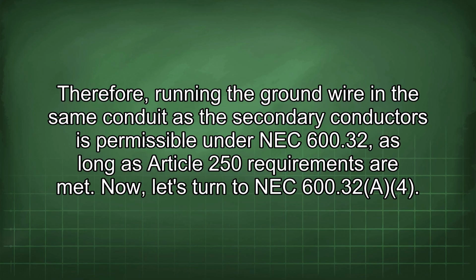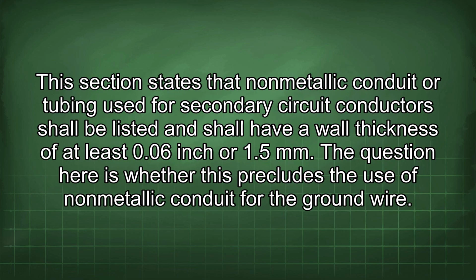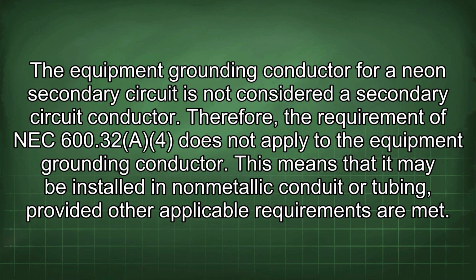Now let's turn to NEC 600.32(A)(4). This section states that nonmetallic conduit or tubing used for secondary circuit conductors shall be listed and shall have a wall thickness of at least 0.06 inch or 1.5 mm. The question here is whether this precludes the use of nonmetallic conduit for the ground wire. The equipment grounding conductor for a neon secondary circuit is not considered a secondary circuit conductor. Therefore, the requirement of NEC 600.32(A)(4) does not apply to the equipment grounding conductor. This means that it may be installed in nonmetallic conduit or tubing, provided other applicable requirements are met.